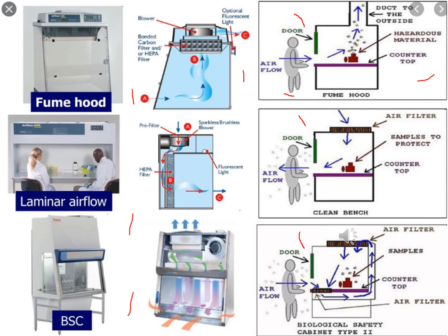The most important thing is to see the airflow. Air enters from here and the exit is on this side. You can see the air goes directly here, moves inside, and then exits through this side. In the case of laminar flow, you can see the air is coming outside. Air enters from here, these are the filters, and here is a sample, and this is the bottom of the bench, and the airflow comes towards this side. So it means that this air going outside does not protect the worker.